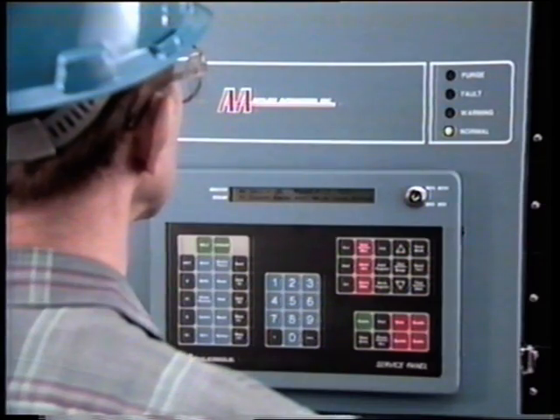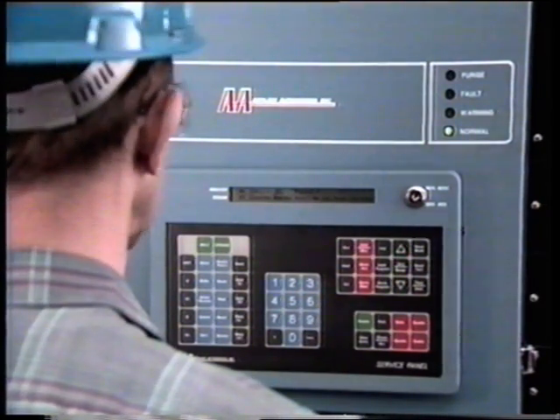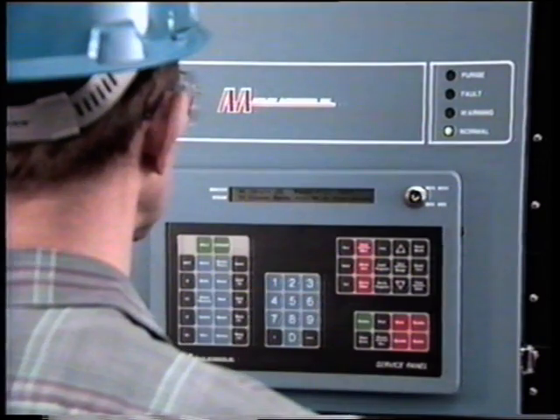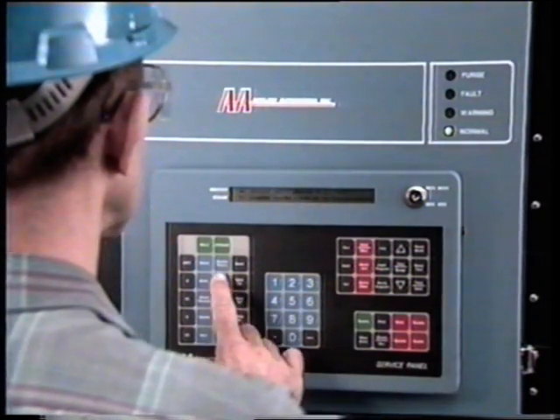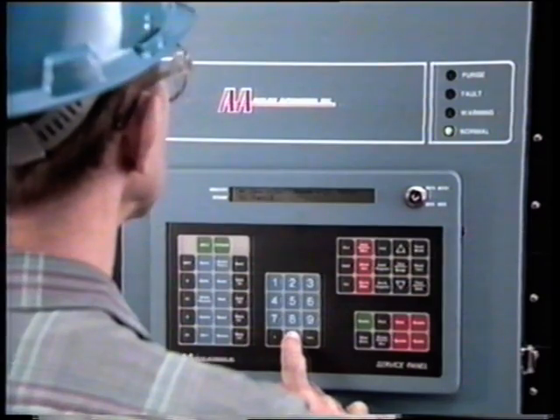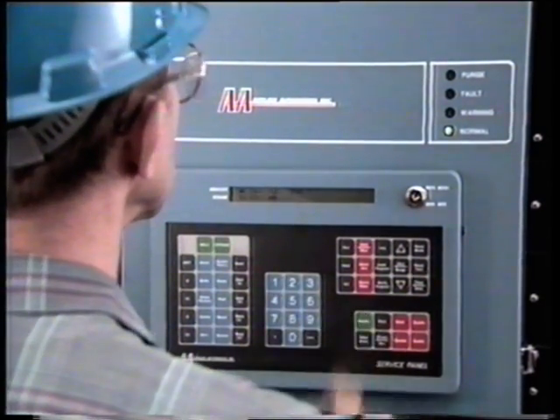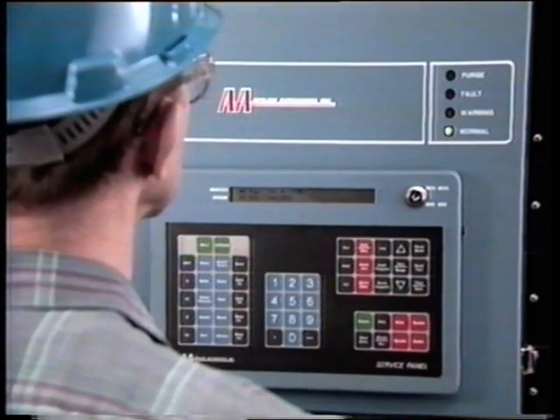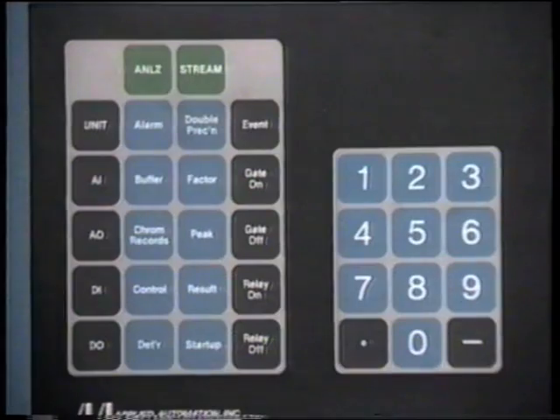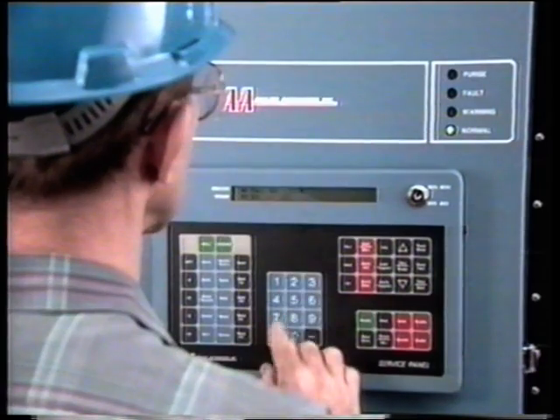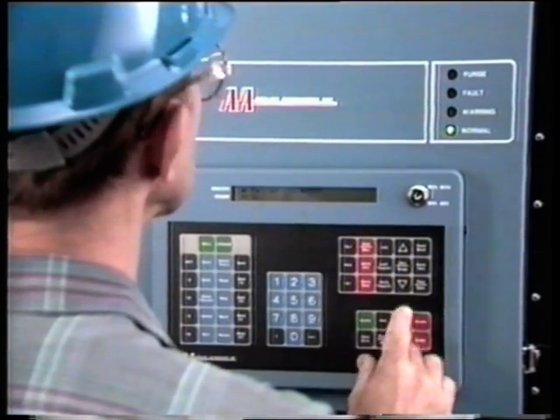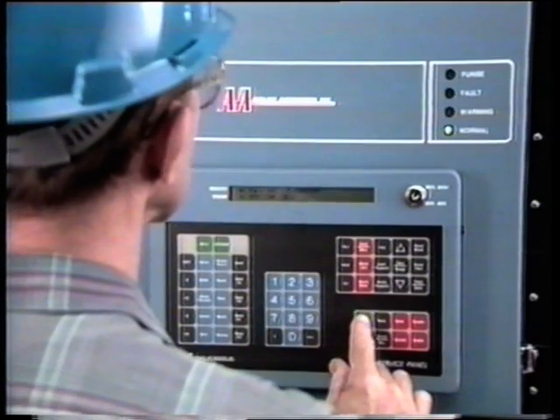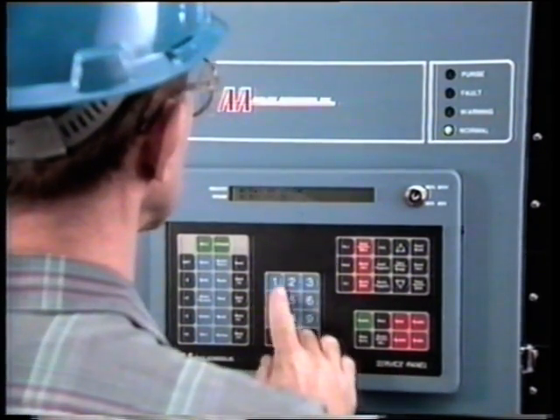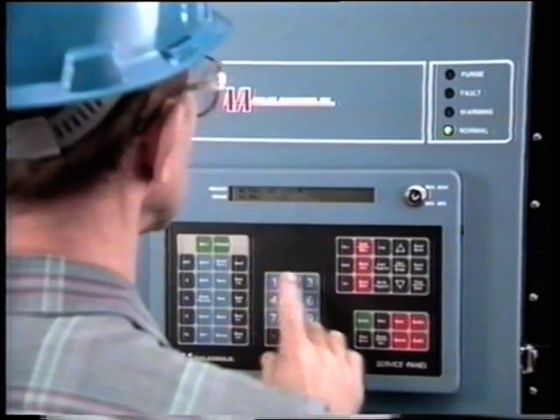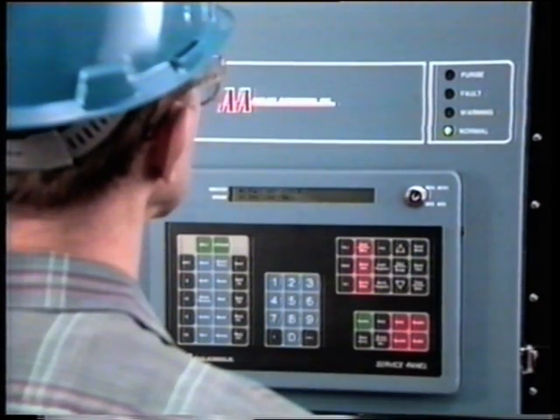Now, check to see that each component in your calibration standard is correctly entered in the analyzer factor table. To do this, press Factor, 1, 0, 1, and Display. The display will show the current factor, 101. To change the concentration, enter your calibration standard for peak 1 and press Enter. To read and change the next concentration, press Display and enter the calibration standard. Repeat this process for each component in your calibration standard.